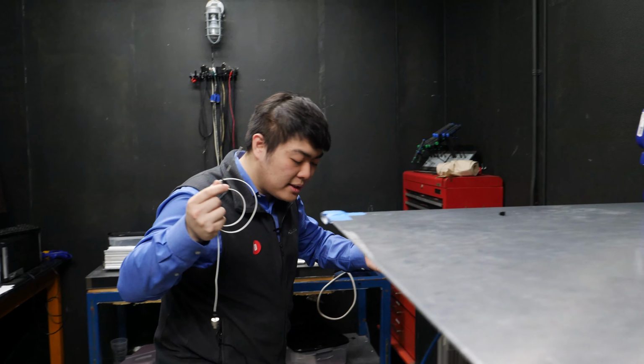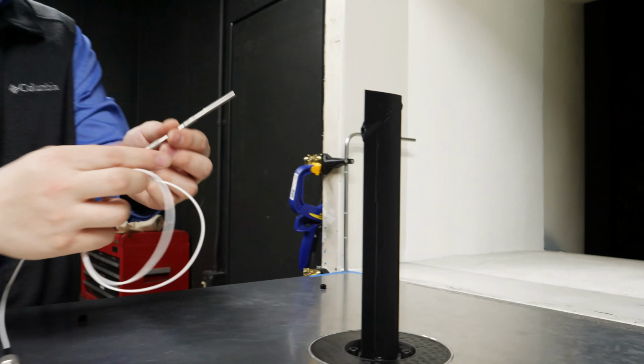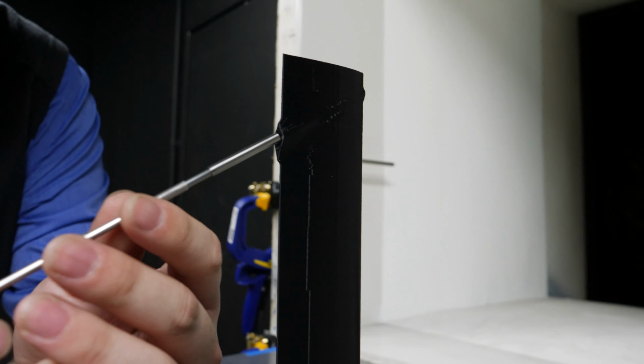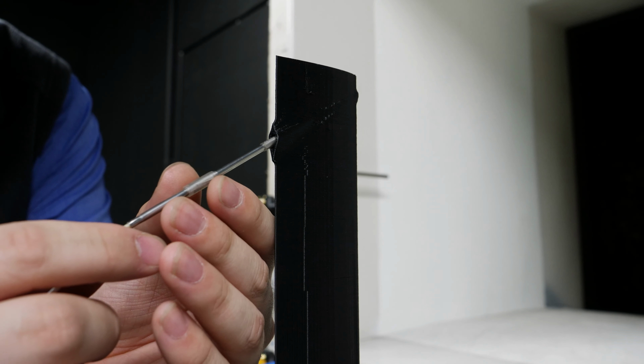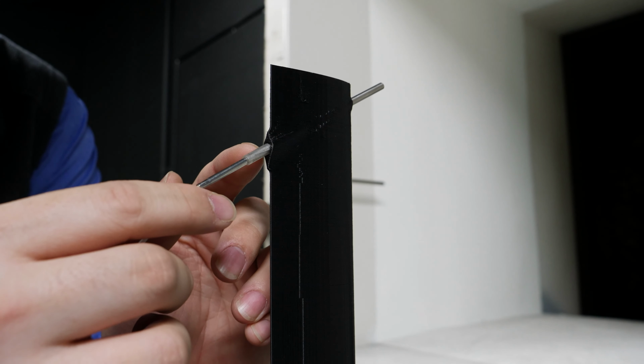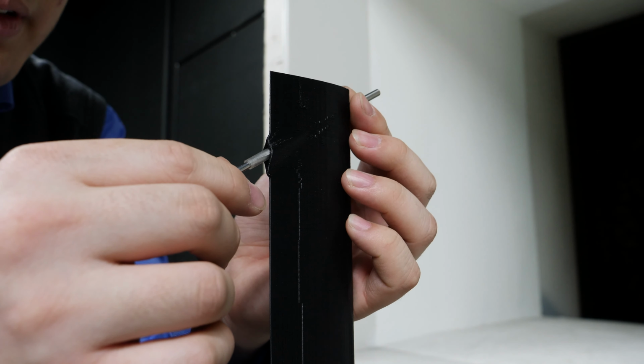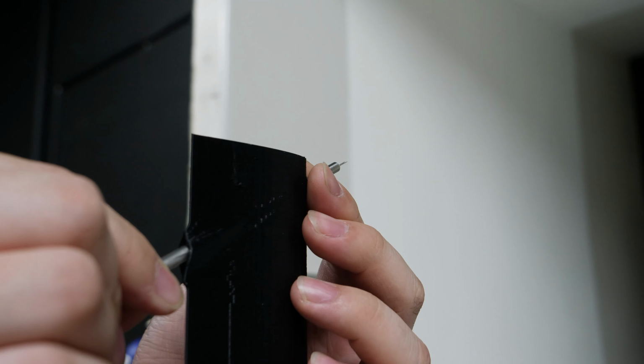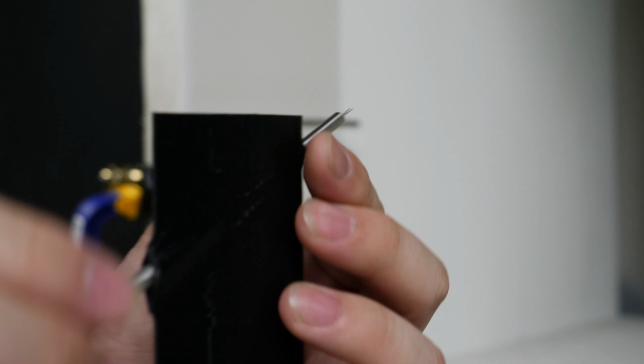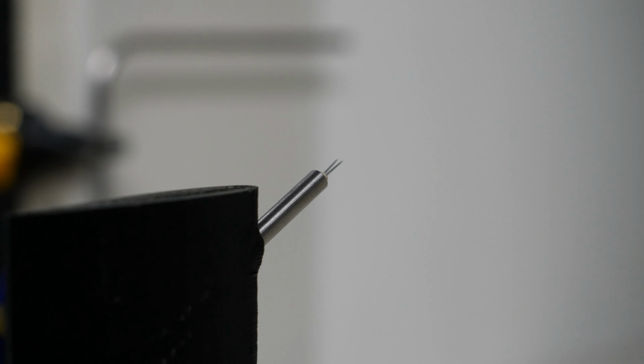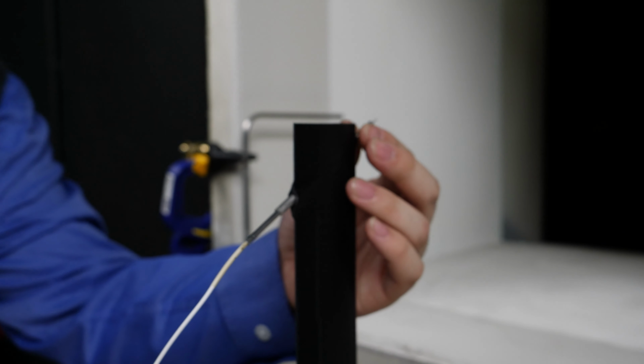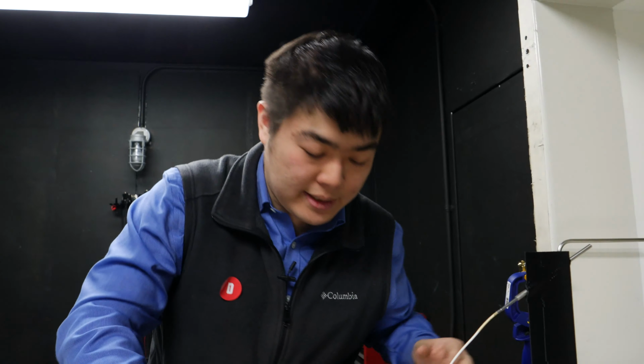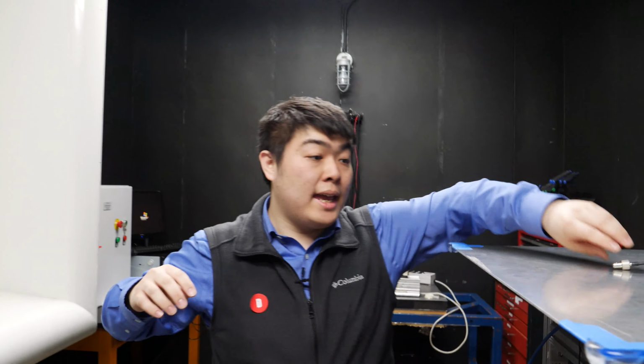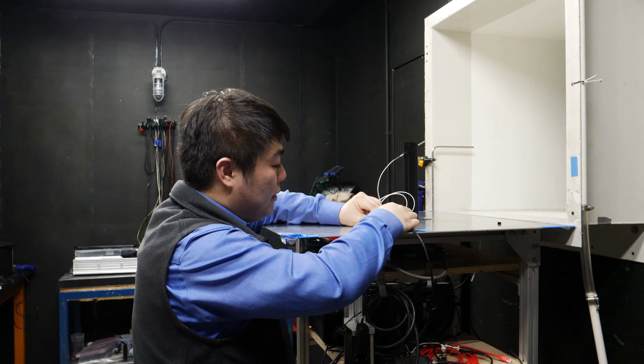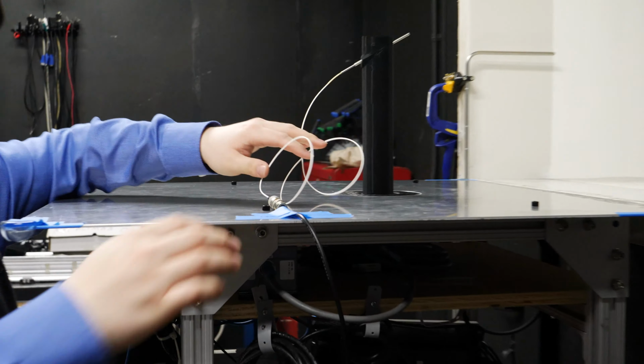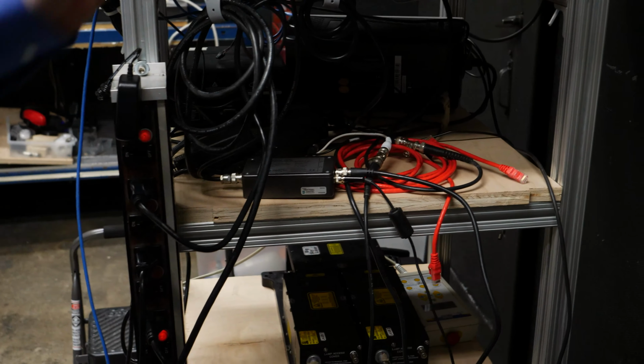So now let's mount the hot wire on the sensor mount. So you're gonna do it very slowly. You're gonna pop the hot wire in here, and then until there's a tape here to stop it. Now you're gonna move it very slowly to expose the hot wire, and then you're gonna rotate the hot wire so that it's perpendicular to the flow, like this. So when everything is mounted okay, we're gonna cover the hot wire since we're not doing testing so far. And then we're gonna connect the cable here to the mini CTA, and it will read the data from the hot wire.